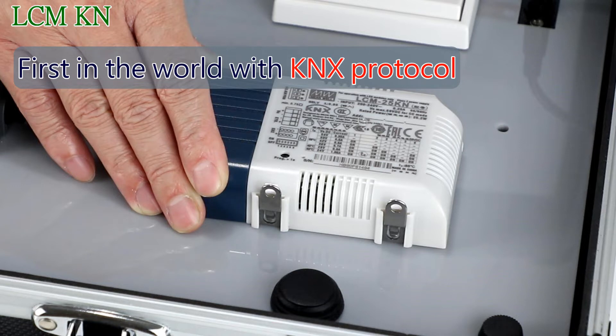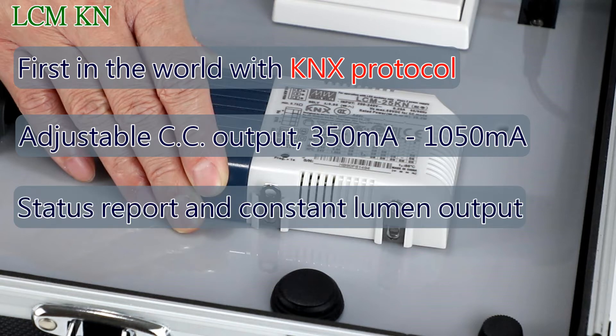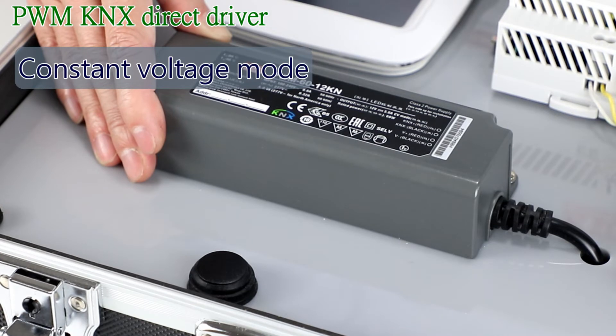The LCM-KN series is the world's first KNX direct control constant current LED power supply. Digital lighting control can be performed without the need for KNX to DALI gateways. Different output currents can be switched with real-time energy consumption, working hours, and lamp failure reports. Light output and temperature compensation can be set, and emergency lighting and synchronous dimming are supported, making it suitable for office and architectural lighting applications.